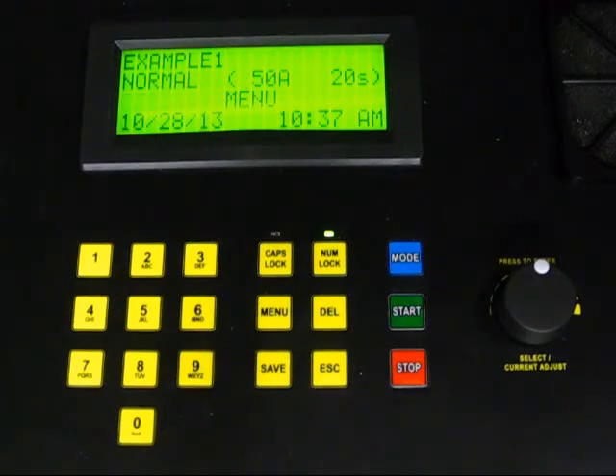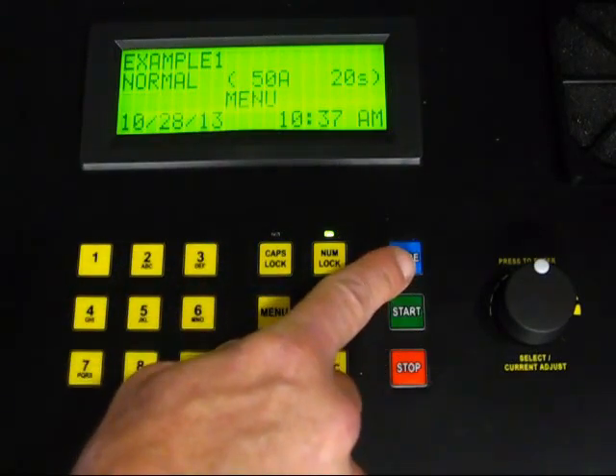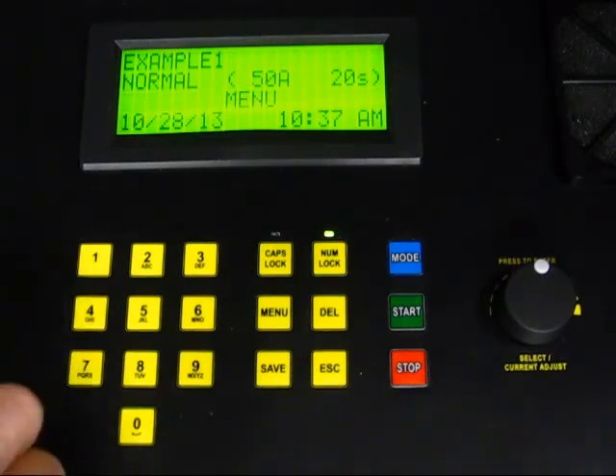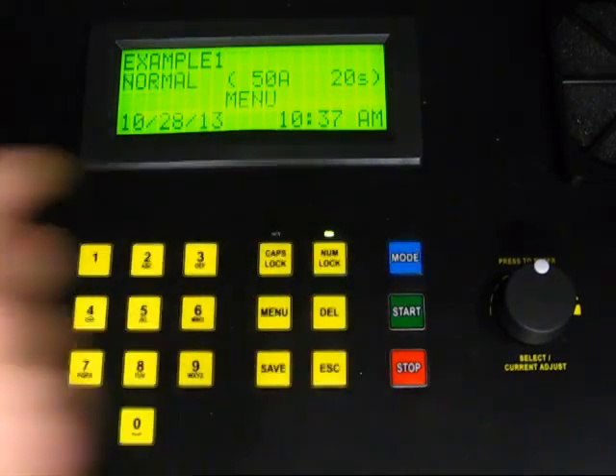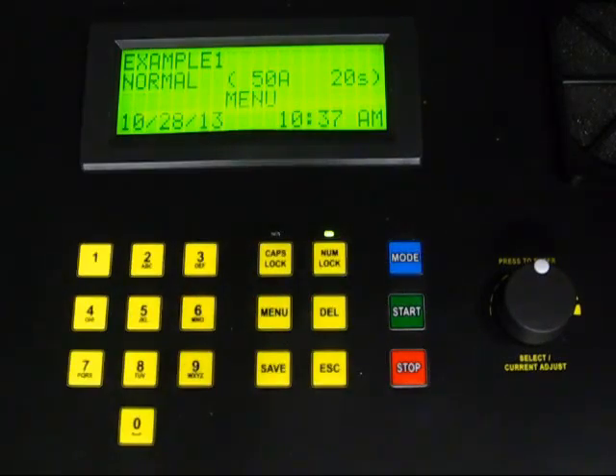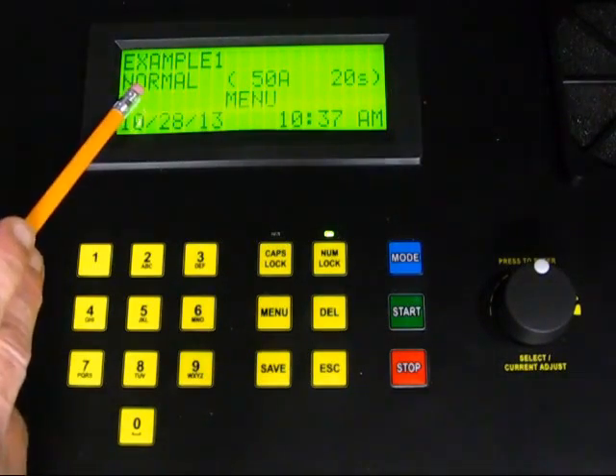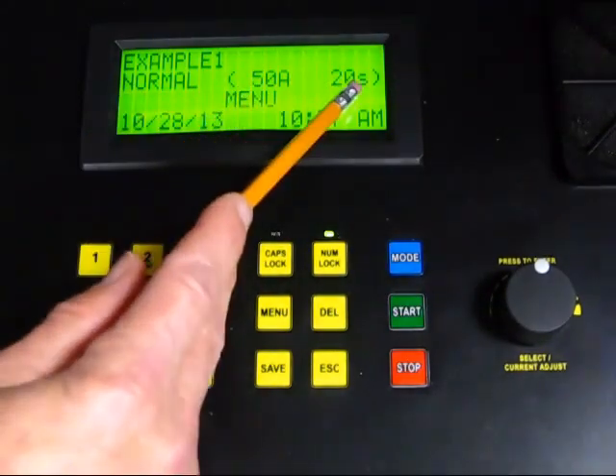We will then press the Menu button to return to the main screen. The final step in setting up the test is to select the test mode. There are two options: Normal and Both Sides Grounded, represented on the display as BSG. You select the mode by pressing the blue Mode button. In our test, we will select Normal Mode. The display will now indicate that we are ready to run the test. The name of the object that will contain the test appears at the top of the screen. The second line shows that we are running the test in Normal Mode at 50 amps for 20 seconds.